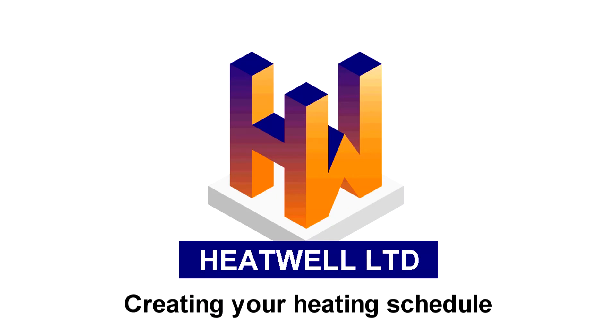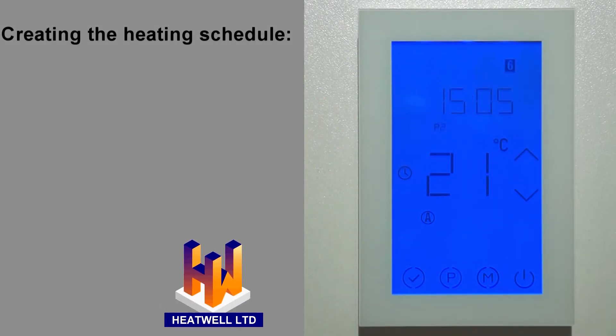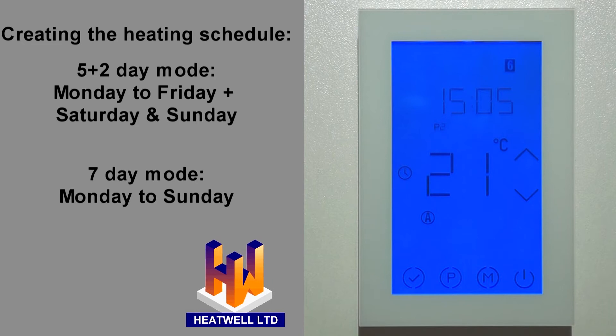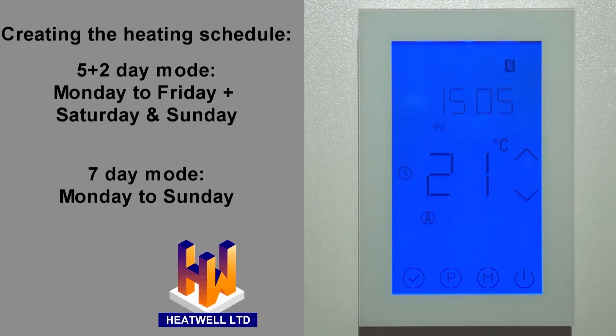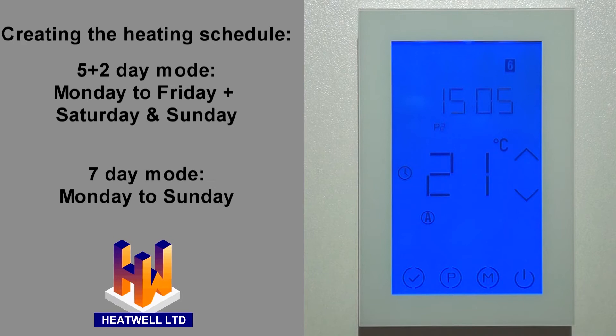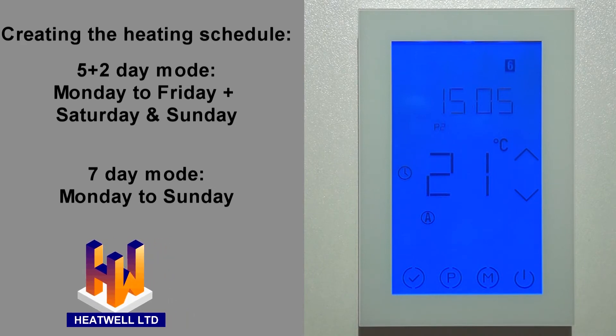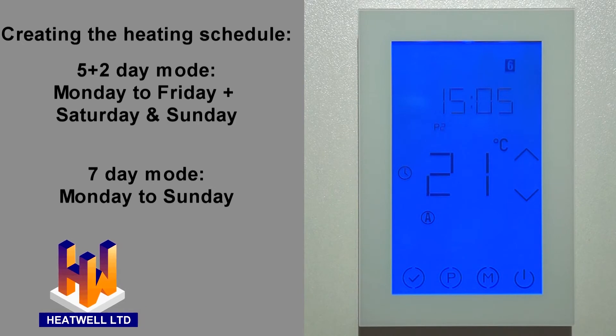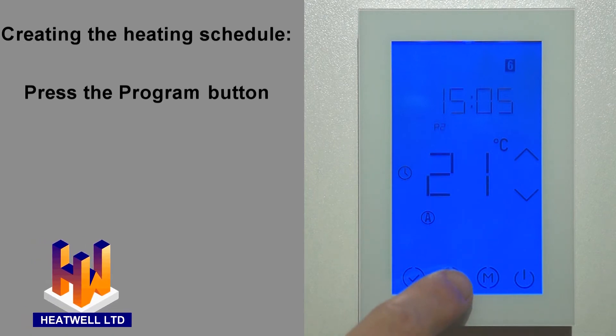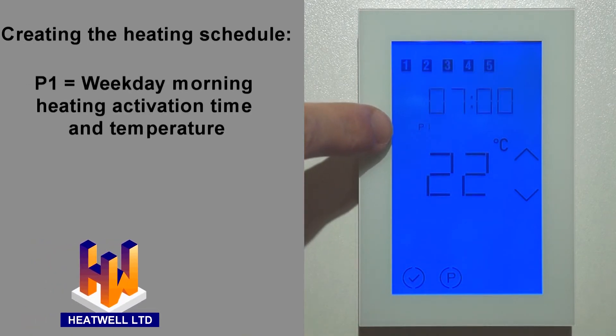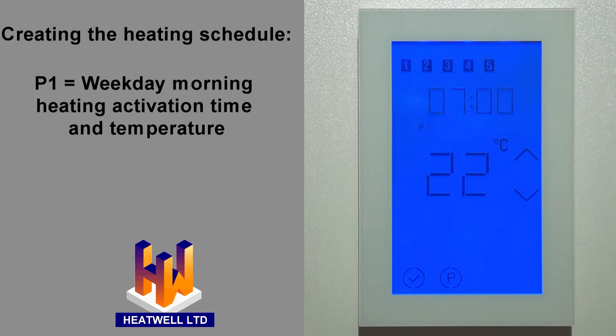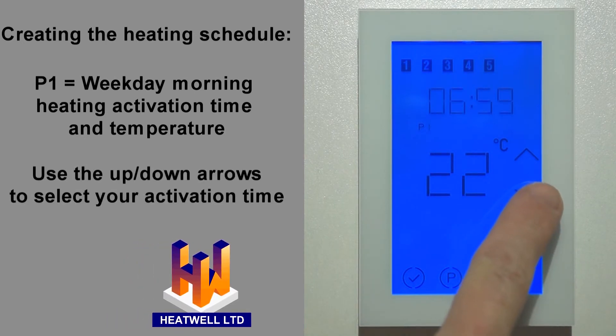Creating your underfloor heating schedule. The thermostat has two schedule options: 5 plus 2 day mode, which is the default setting, or 7 day mode. On 5 plus 2 day mode, you can choose heating temperatures and times for the 5 weekdays and different temperatures and times for the weekend. 7 day mode applies the same switch-on times and temperatures every day. Let's begin by programming the heating schedule for 5 plus 2 day mode. Start by pressing the program button. P1 will be displayed. P1 is your first activation time for your underfloor heating. In this case, we'll have the floor heating turn on at 6:30 every weekday morning by using the up and down arrows.